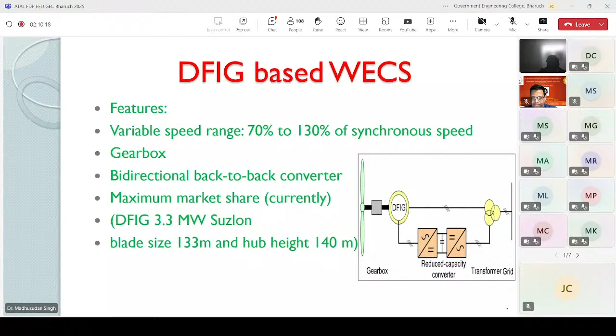The grid side converter has simply to maintain the DC link voltage and also to ensure UPF operation for either side of power flow. Because if it is subsynchronous operation, the rotor draws power from the grid; otherwise it supplies power to the grid. So in both cases, it can ensure UPF operation through GSC.